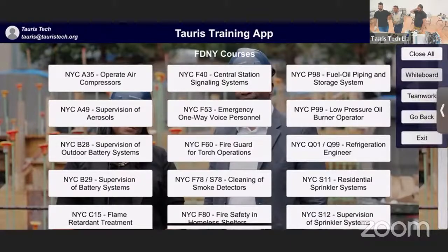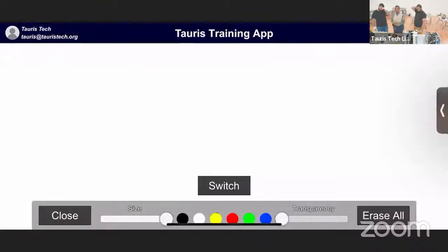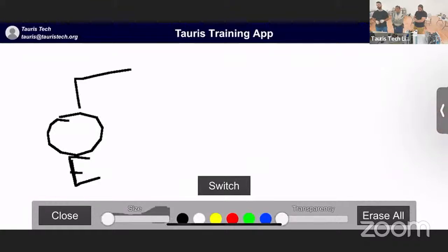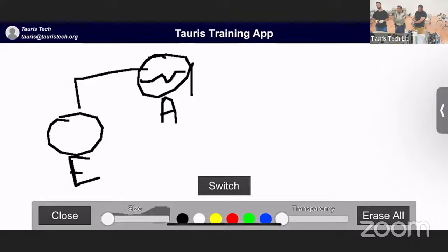So let's see. In an absorption system, you have your evaporator, and the evaporator is going to be attached to something called an absorber. Inside of the absorber, you're going to have some type of fluid that attracts another fluid. Now, he said they had an ammonia system. So this is lithium bromide. Lithium bromide is salt. So inside of the absorber, you have salt water. It's called solution. So you have your solution inside of the absorber.